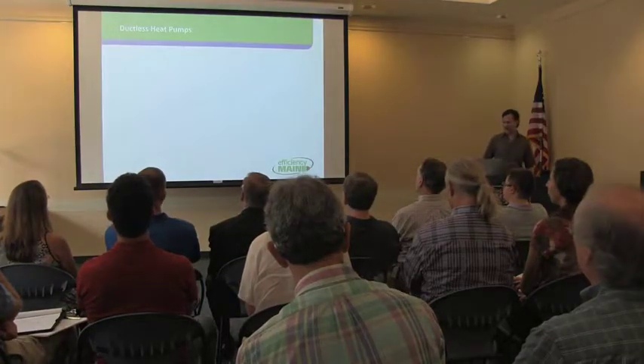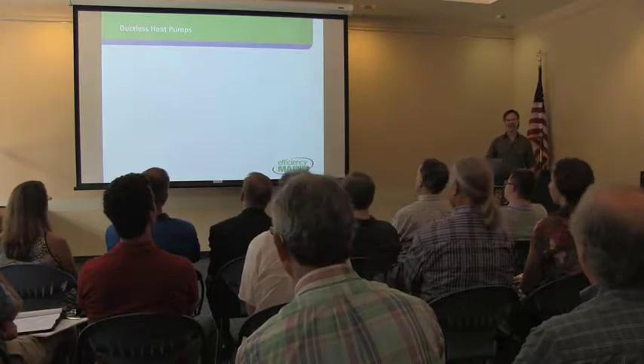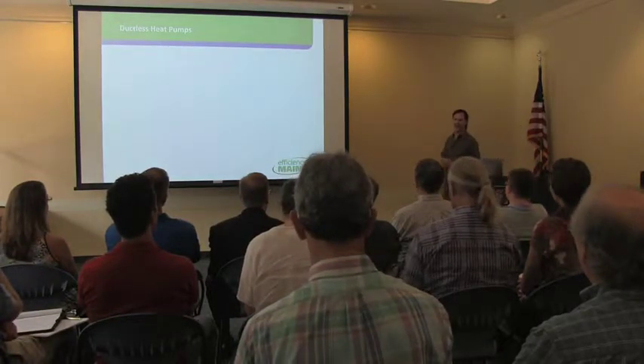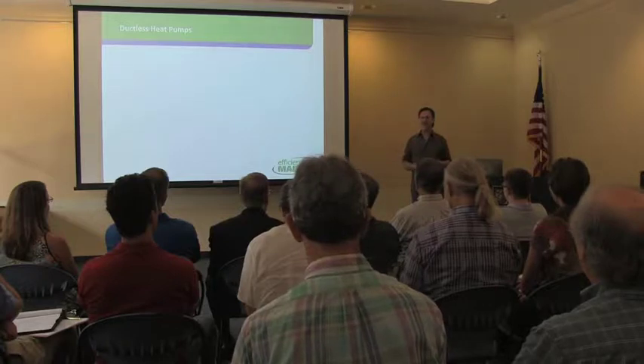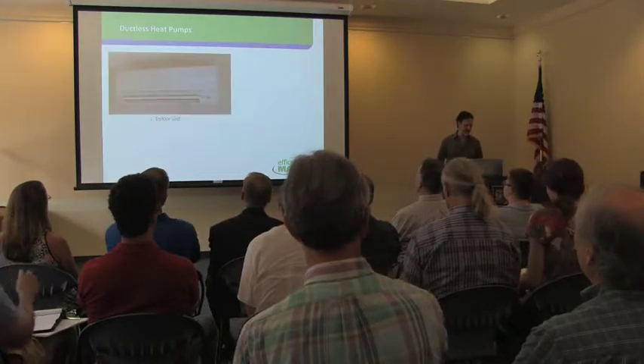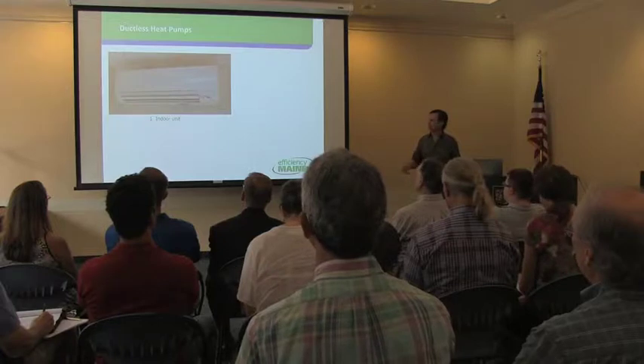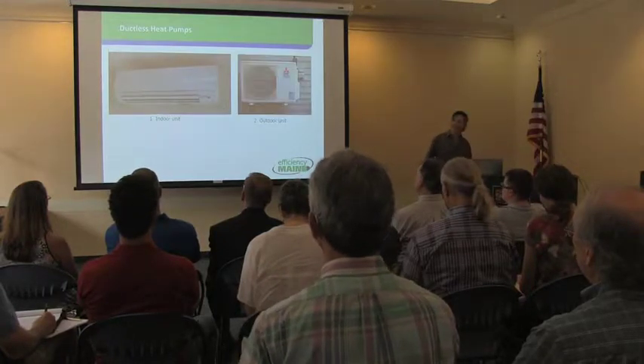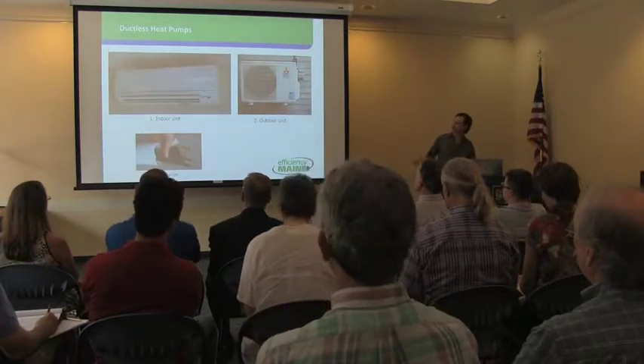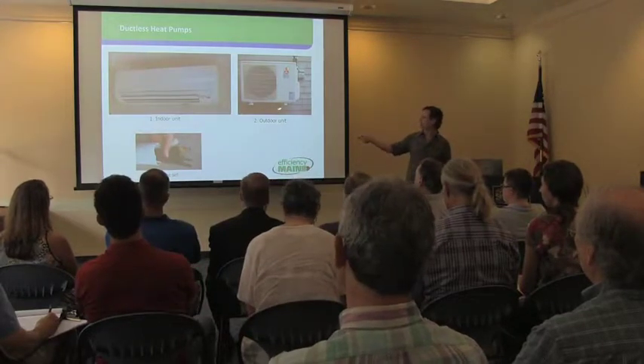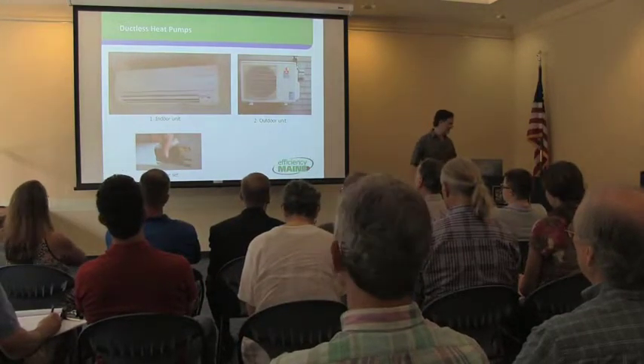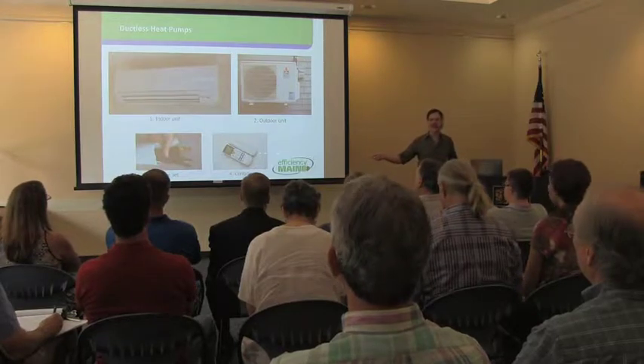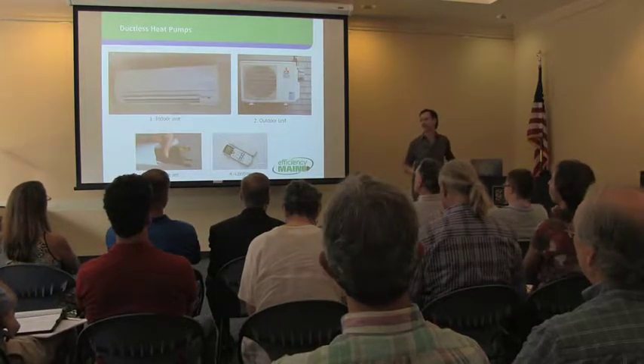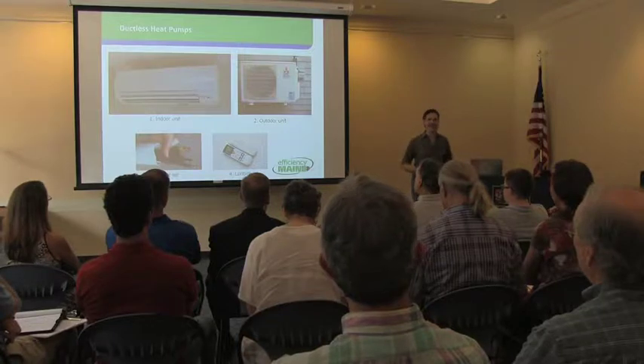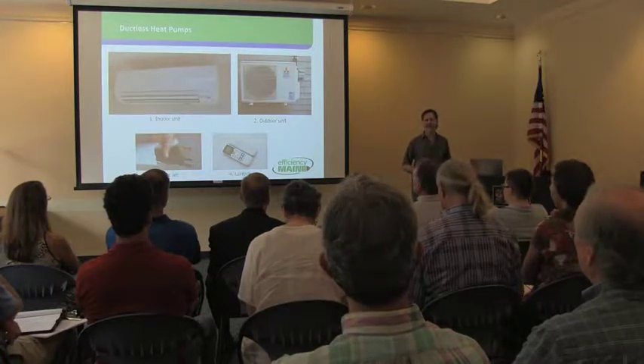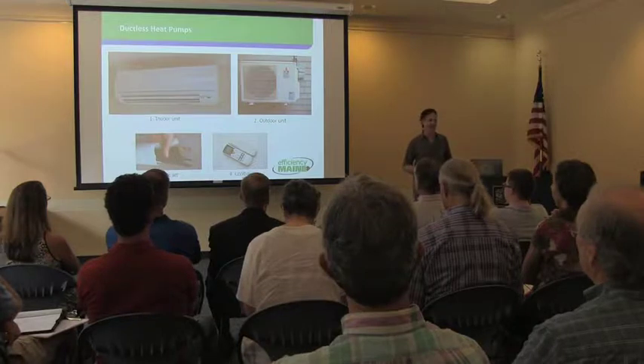A colleague of mine had a good slide that sort of showed ductless heat pumps. And I'm not here just to talk about ductless heat pumps, but a lot of the new air source heat pumps that are going in are ductless. And the basic way it works is there's an indoor unit, there's an outdoor unit, there's a collection of pipes and wires that run between the two called the line set, and then there's some sort of control. And most of these units have a handheld remote, just like your TV. You tell it to run warmer or run cooler, turn on, off, turn the fan on, whatever you want to do with that remote control.